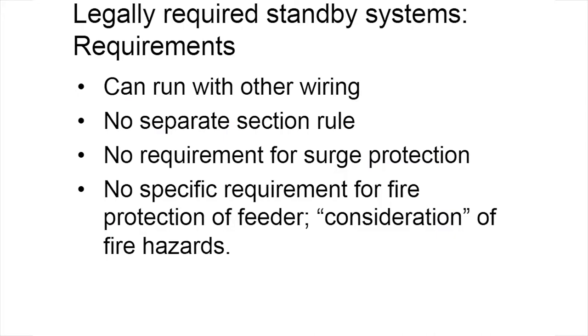Legally required standby circuits can run in the same raceway as general wiring. There's no requirement for separation from other wiring, and that's in contrast to the requirements for emergency systems. There's also no requirement that legally required standby circuits occupy separate vertical sections of switchboards or switchgear in order to be served from a single generator feeder. That requirement exists for emergency systems, but not for legally required standby. And there's no requirement for surge suppression. Article 701 does require that certain various hazards, and that would be including fire, be considered in the design of the system, but there's no specific requirement for circuit fire protection.